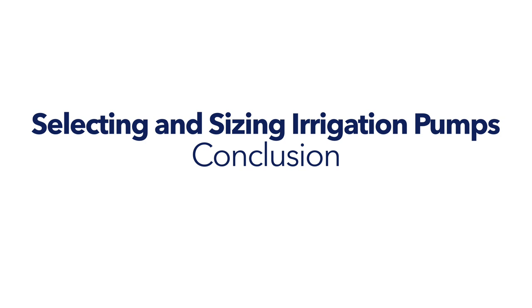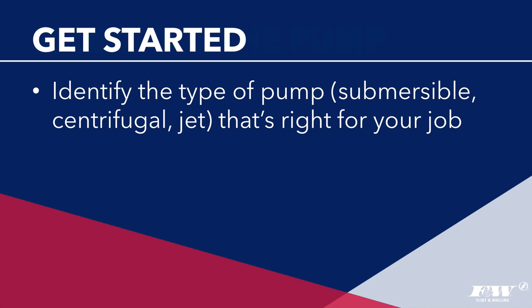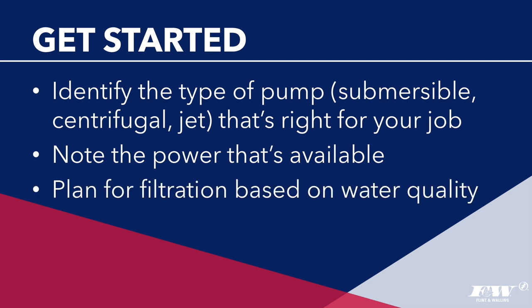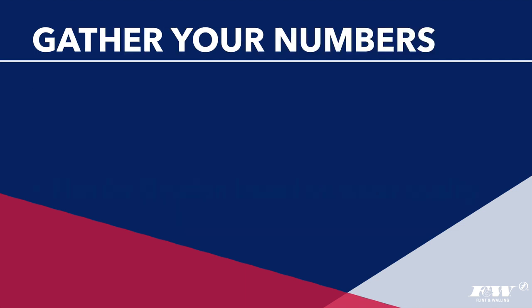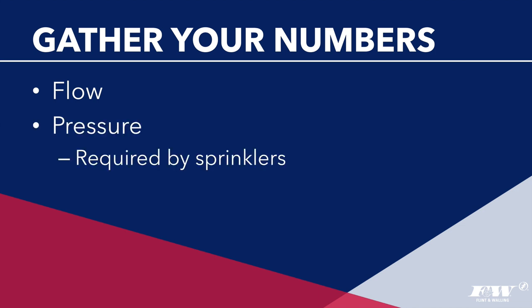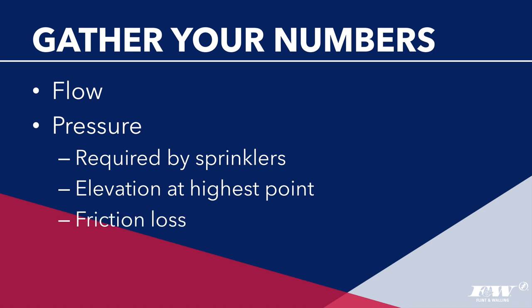Selecting a pump boils down to knowing what kind of pump you need and then knowing the pressure and flow requirements. To review the steps: identify the type of pump (submersible, centrifugal, jet) right for your water source; note the power available (120 or 220 volt, single or three phase); plan for filtration based on water quality; calculate the maximum flow rate in GPM and the total pressure requirements — including sprinkler pressure, elevation, friction loss in pipe/fittings/valves, and suction lift. Then use the pressure and flow rate to locate your needs on a pump curve, select the curve containing your point, and you're ready to order your pump.